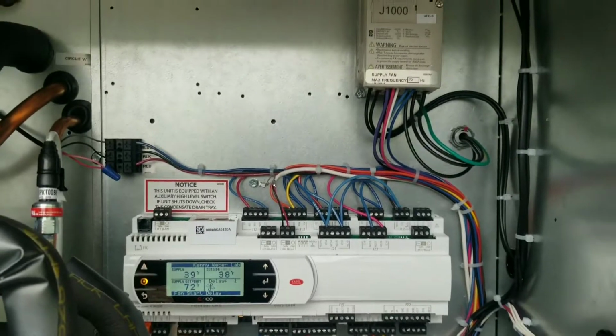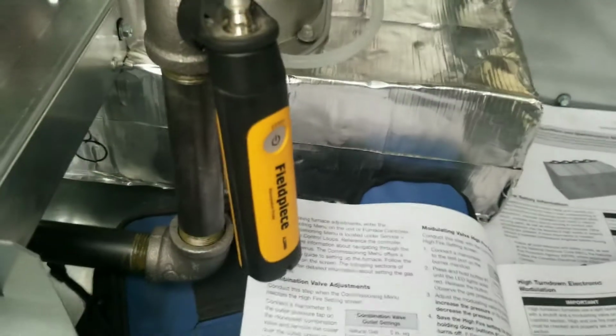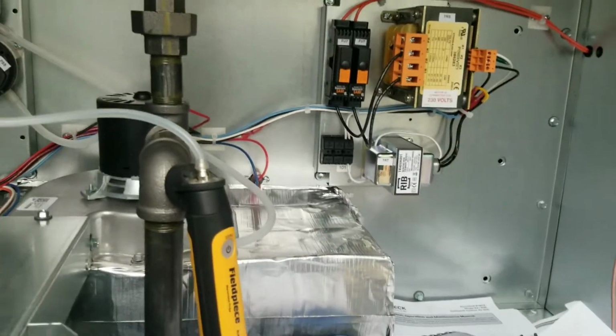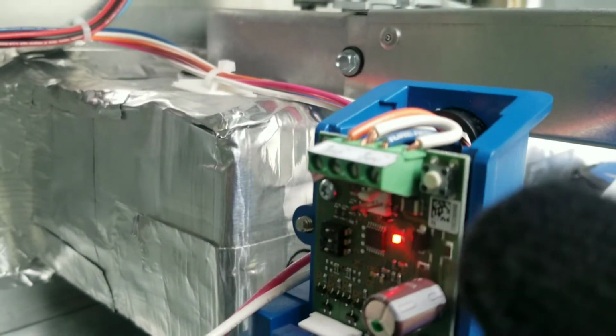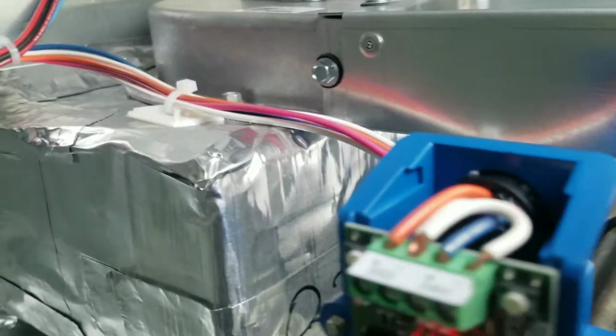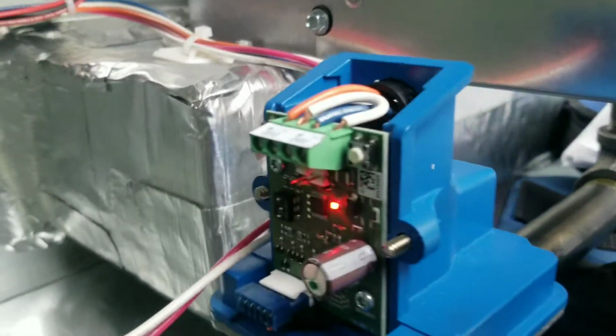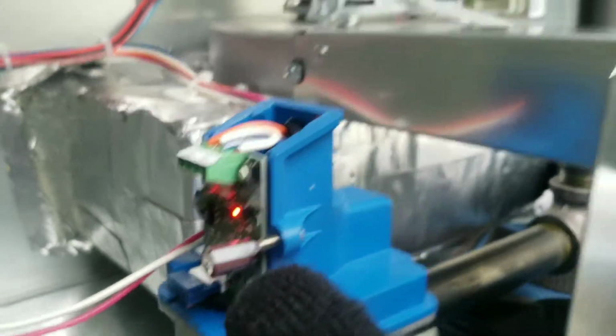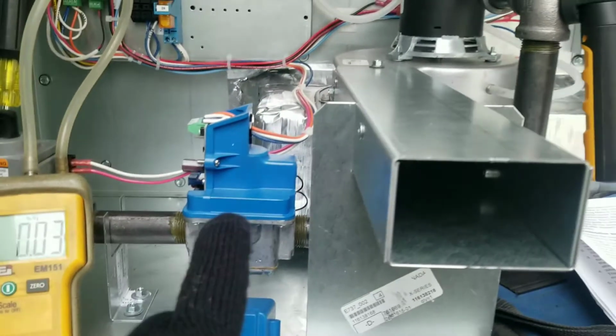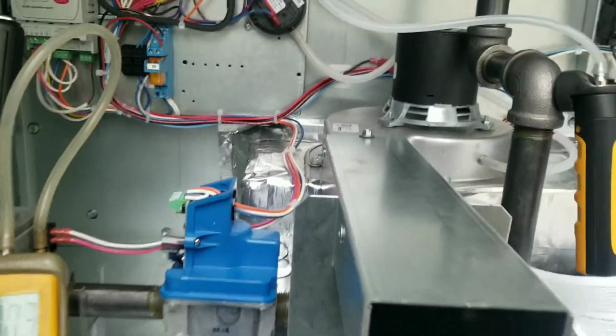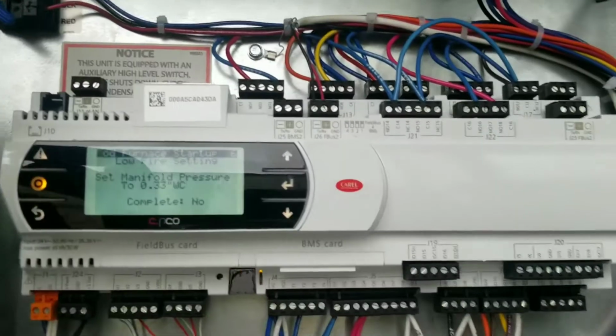Just give it a minute. Let me check rotation. I'll bring you guys back for the gas. So I learned something here, guys. Basically the control walks you through everything, but this modulating valve, I haven't seen one of these yet. Got a button there and a button on that back side. Press and hold till the light comes on, and then you can adjust the outlet pressure with those buttons up and down. So the control walks you through and tells you what to set everything at.